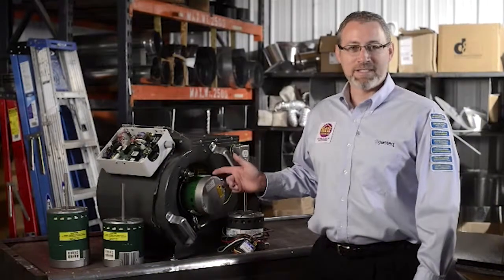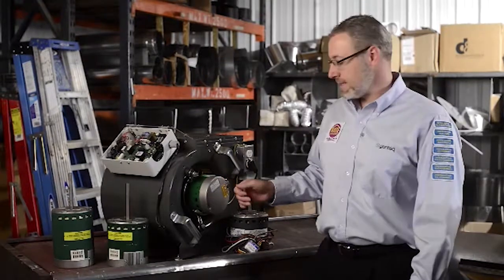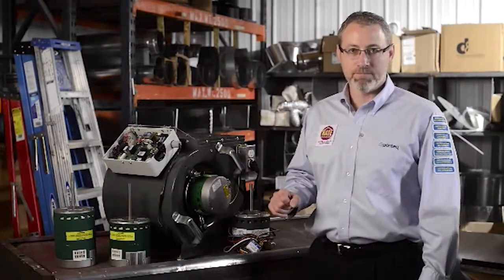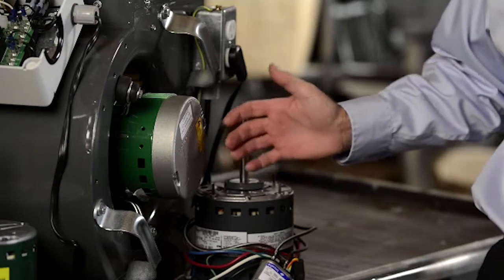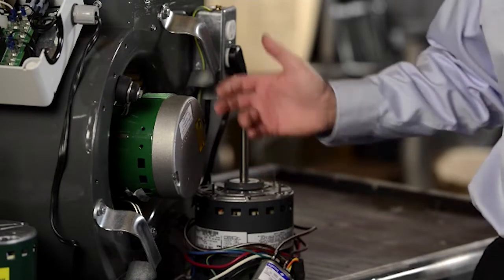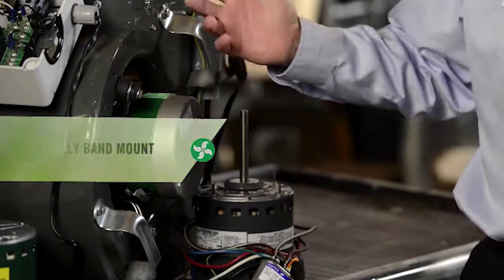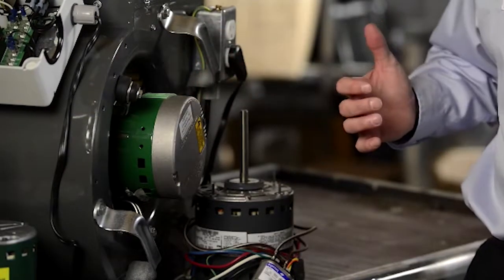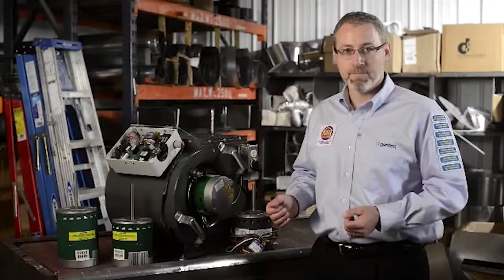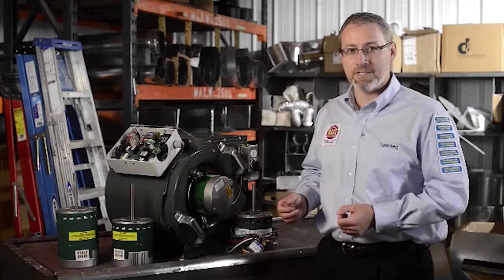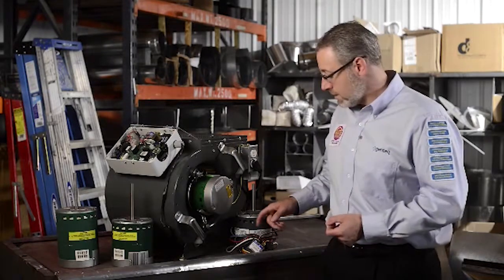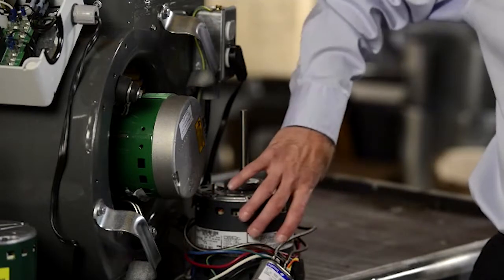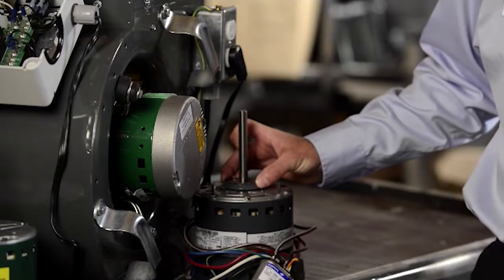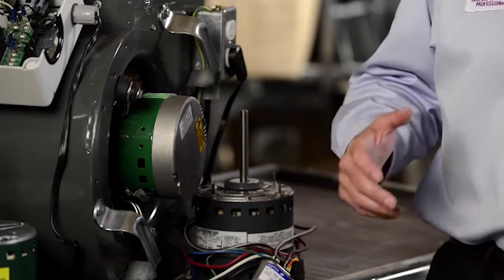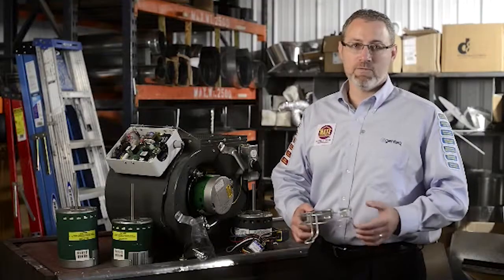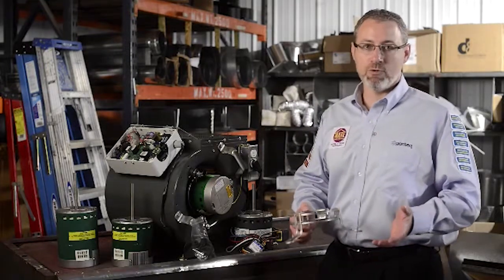The Evergreen IM is a NEMA 48 frame motor, meaning that it's approximately 5.6 inches in diameter. If your existing PSC motor is also a NEMA 48 frame motor, and it's installed in a belly band style mount, you can simply loosen the bolt on the mount, take out your PSC motor, and slide in the Evergreen. If your existing PSC motor is not a NEMA 48 frame mount, or the mount is welded to, bolted to, or connected around the bearing portion of the PSC motor, you are going to need a new universal replacement motor mount. Any universal motor mount that you use is going to have to match two criteria.